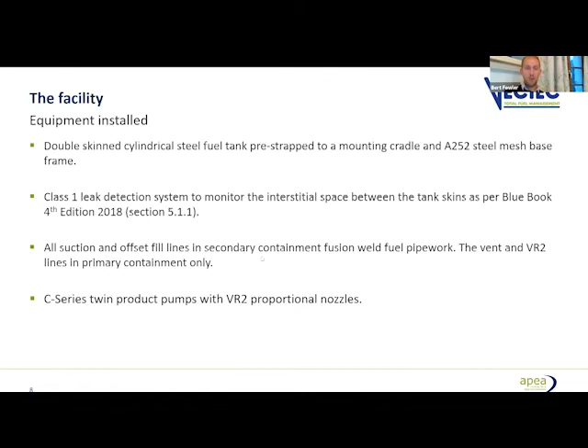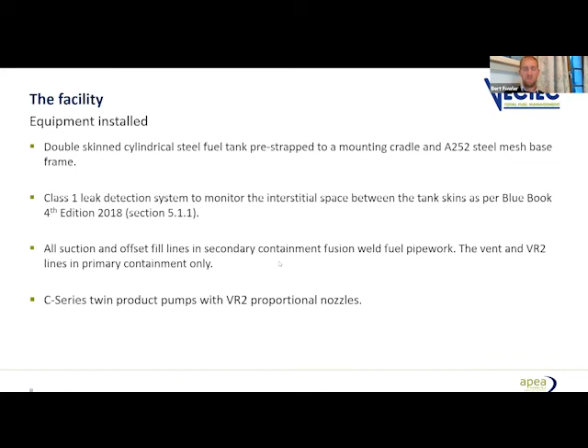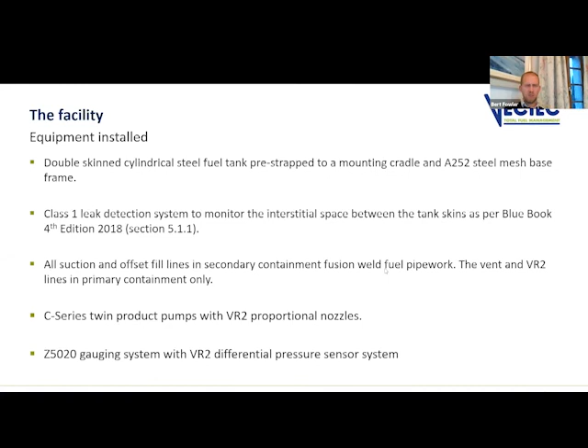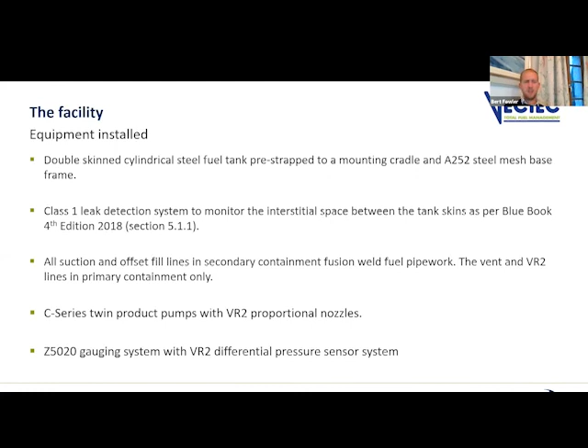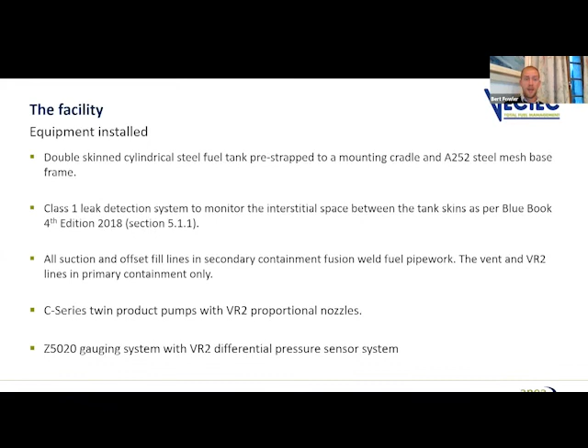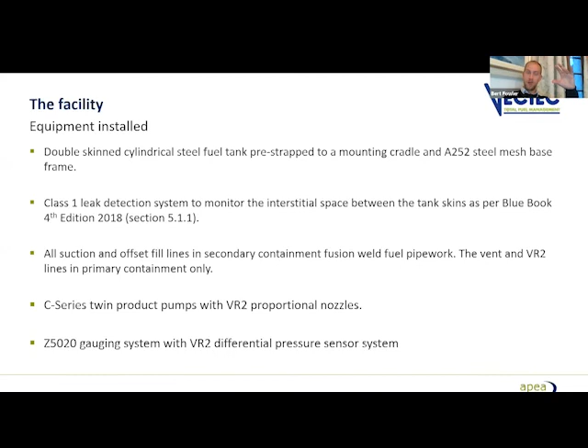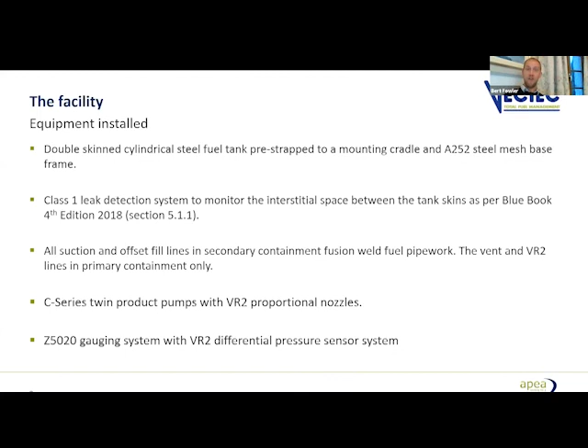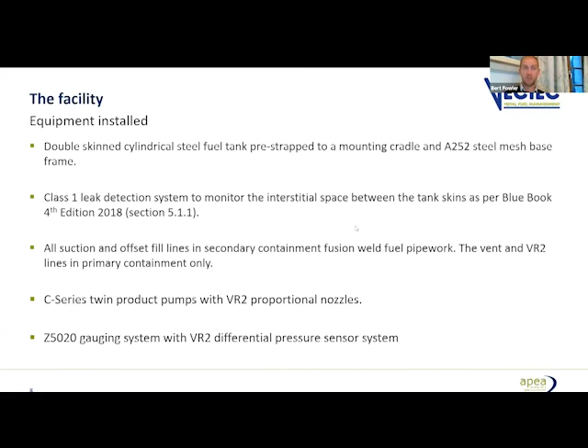The pumps being used are Pumptronics C series with stage 2 vapor recovery proportional nozzles - not a great number of UK manufacturers currently make stage 2 vapor recovery commercial pumps. Finally, the gauging system has to be ATEX rated, which is quite specific with vapor recovery. The sensors used on this one are from OLE - it's a differential pressure system. Essentially you have two sensors: one sits at the top of the tank and takes the pressure of the petrol vapor, and the other sits near the bottom and takes the pressure reading of the liquid. One subtracting from the other, I'm reliably informed, provides your differential reading, which gives you your literage and ullage calculations.